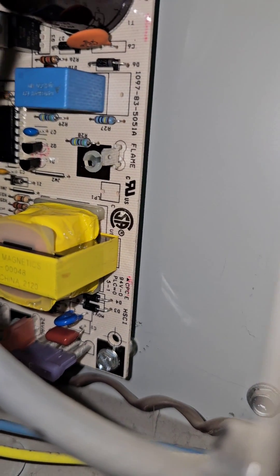Let me show you on this unit heater above where the AC signal comes from, and then we'll look at the DC microamp reading afterwards. There is our flame sensing terminal right there. I'm going to attach a jumper back to my meter and check it to ground to show you what it reads on that flame sense terminal.